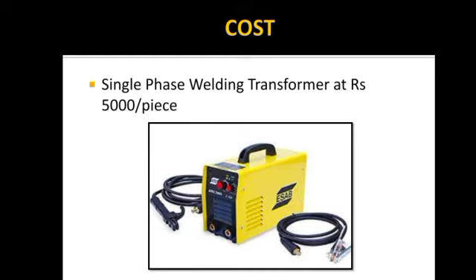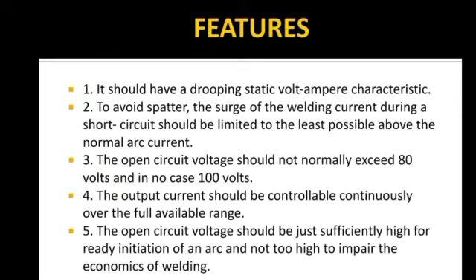Features of transformer: First, it should have a drooping static volt-ampere characteristic. Second, to avoid spatter, the surge of the welding current during a short circuit should be limited to the least possible above the normal arc weld current. Third, the open circuit voltage should not normally exceed 80 volts and in no case 100 volts. Fourth, the output current should be controllable continuously over the full available range. Fifth, the open circuit voltage should be just sufficiently high for ready initiation of an arc and not too high to impair the economics of welding.